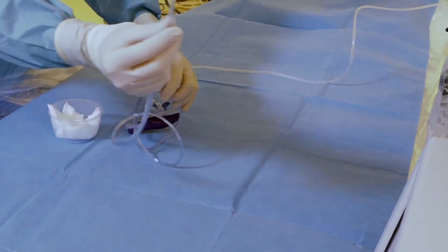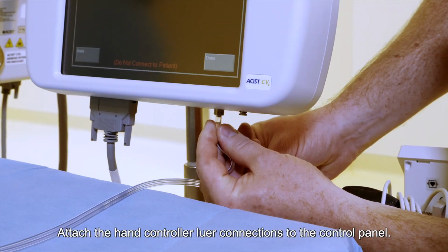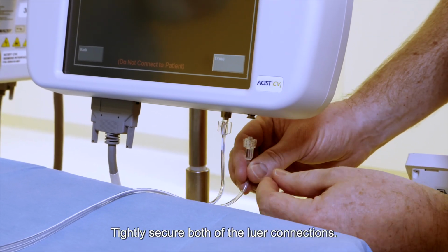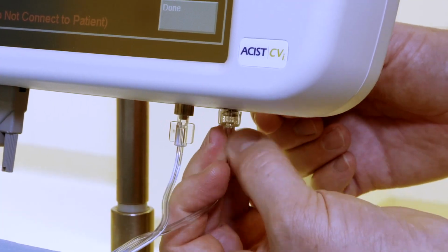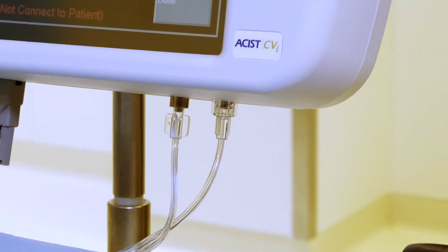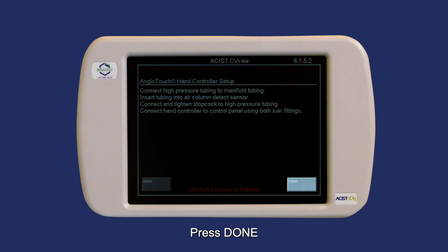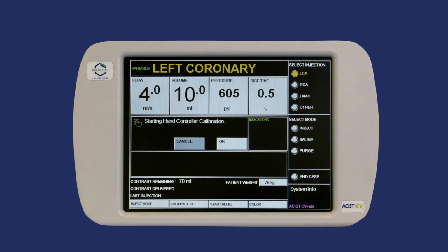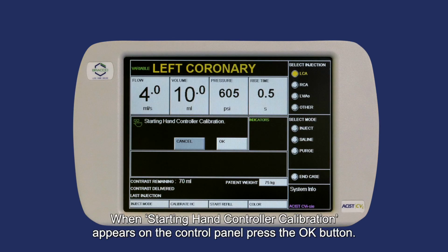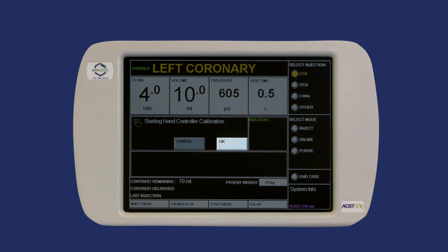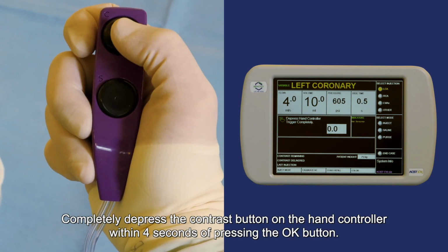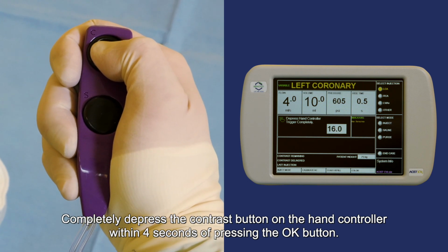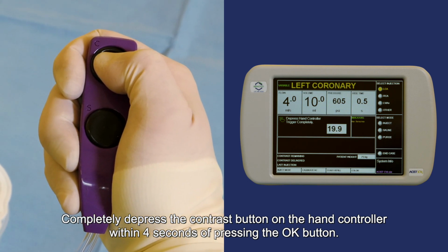Step 4. Attach the hand controller luer connections to the control panel. Tightly secure both of the luer connections. Press Done. Step 5. When starting hand controller calibration appears on the control panel, press the OK button. Completely depress the contrast button on the hand controller within 4 seconds of pressing the OK button.